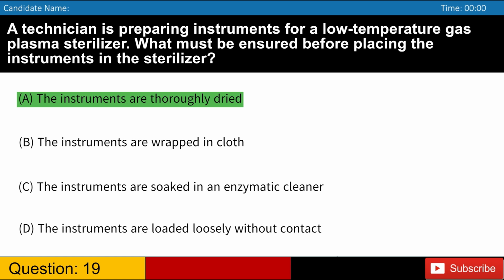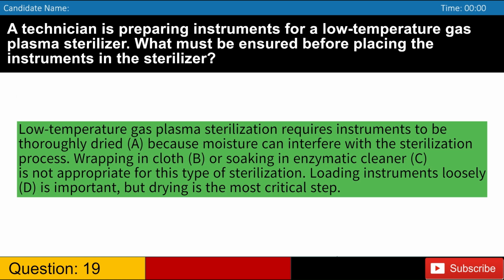Answer, A. Low-temperature gas plasma sterilization requires instruments to be thoroughly dried, A, because moisture can interfere with the sterilization process. Wrapping in cloth, B, or soaking in enzymatic cleaner, C, is not appropriate for this type of sterilization. Loading instruments loosely, D, is important, but drying is the most critical step.